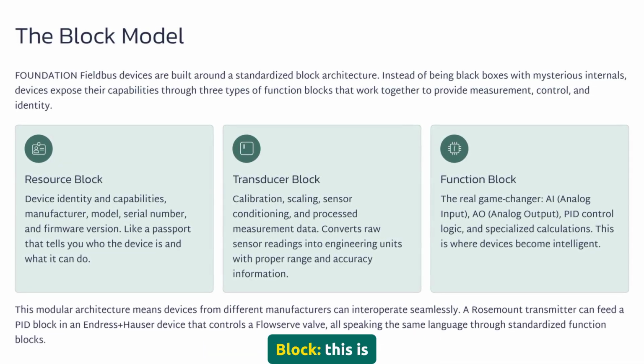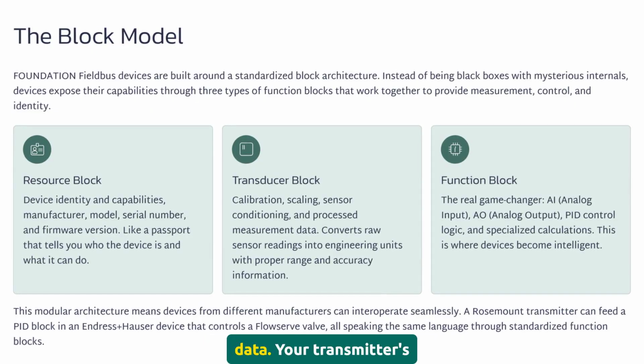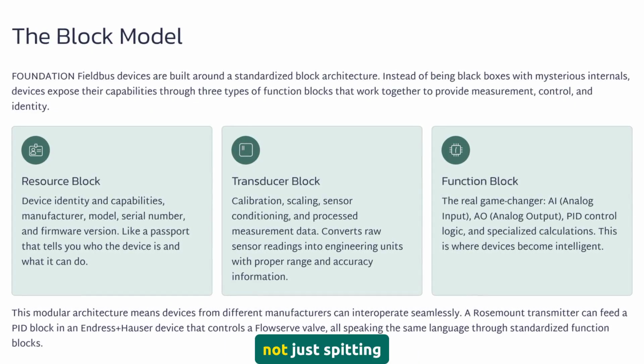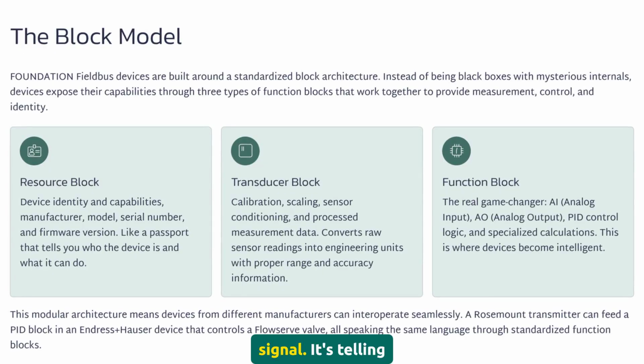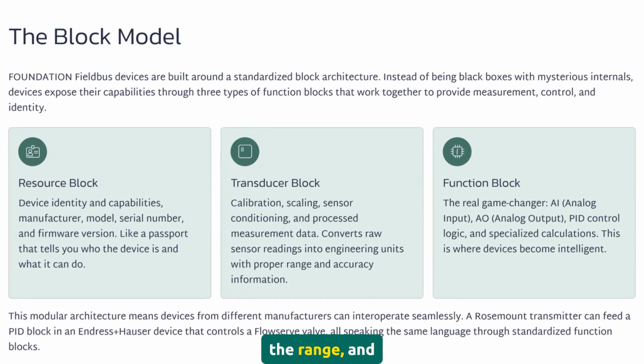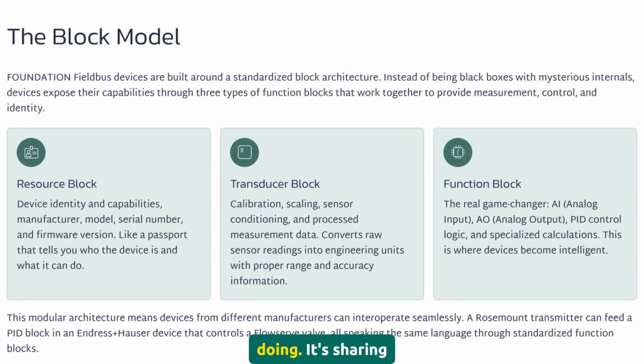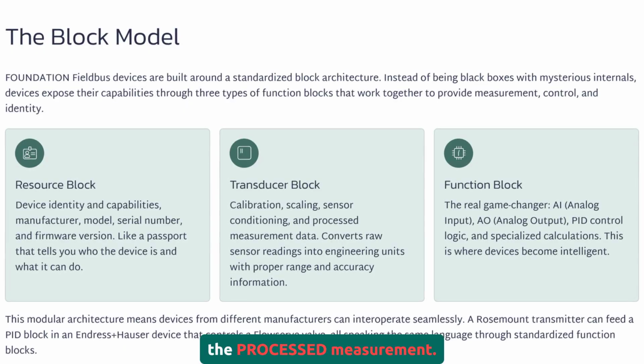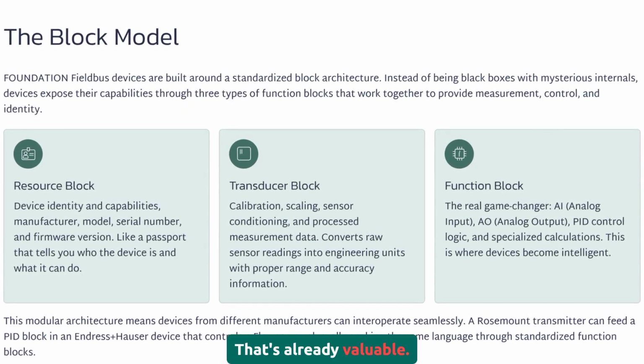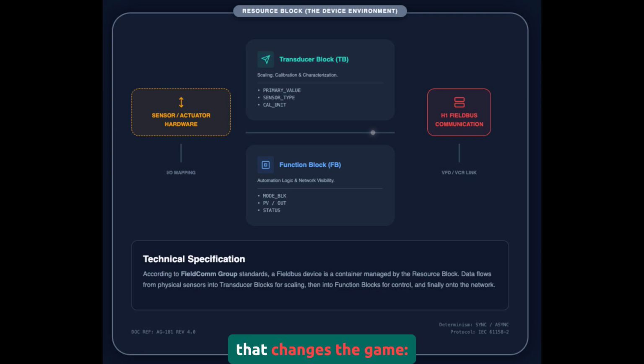Transducer block. This is calibration and measurement data. Your transmitter's not just spitting out a raw signal. It's telling you the scaling, the range, and the linearization it's doing. It's sharing the processed measurement. That's already valuable. But here's the one that changes the game. Function blocks.